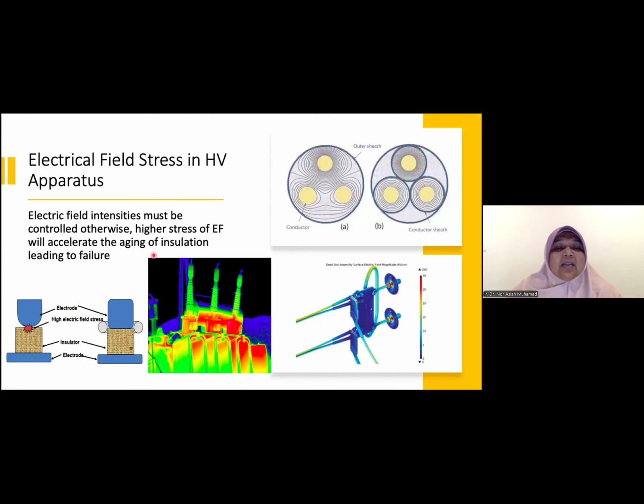So, the electrical field stress in the apparatus. We can see that when we have two conductors, these are the two electrodes, positive and negative conductors, being separated by the insulator. So here we will study the E field. If there is a high E field, it means there is a high potential of breakdown in the insulator. So the insulator must be able to withstand the E field produced here, and by studying the E field, we can select the best insulator and also add more design to channel the E field so we can minimize the E field stress.